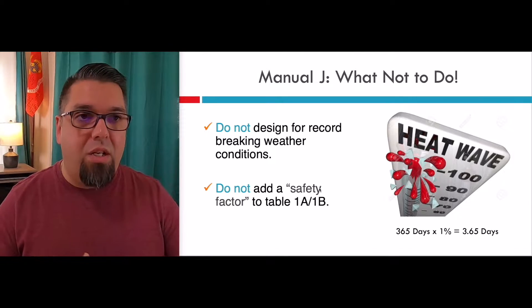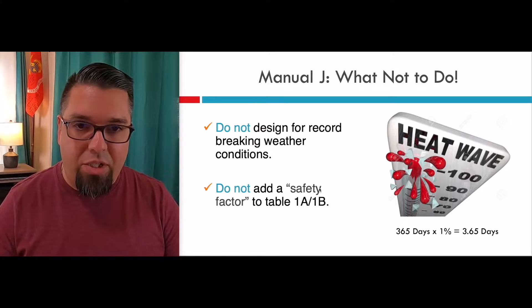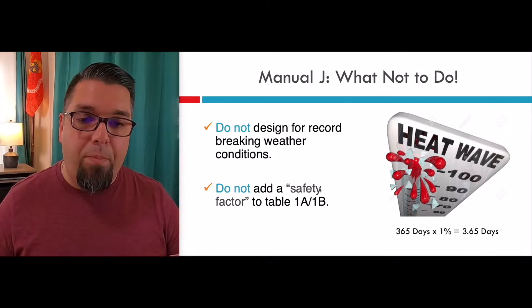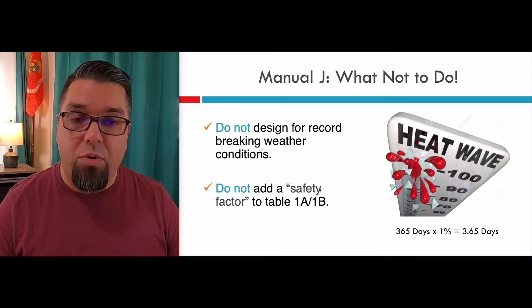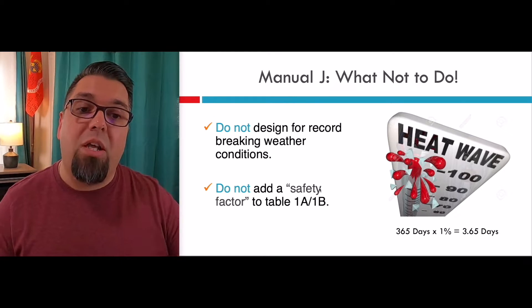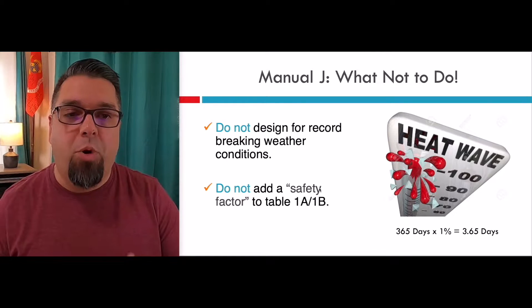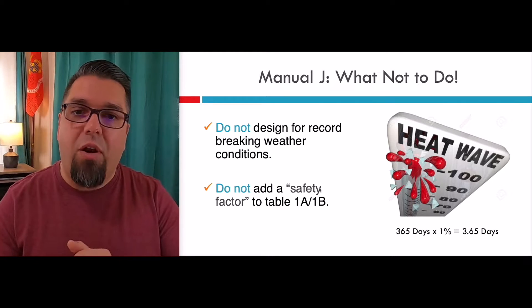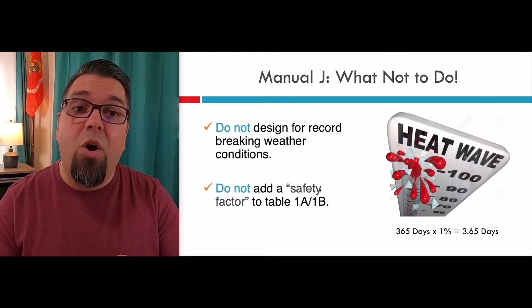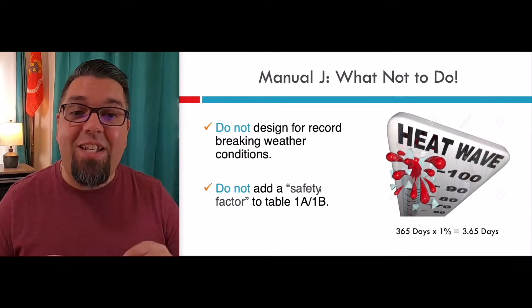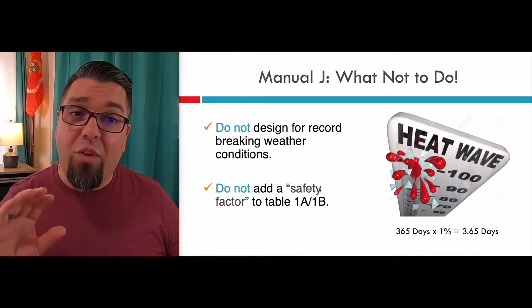We can't keep designing around extreme weather conditions. When there's a heat wave, the system's going to run all the time — prepare your customer for this. It may not keep up by a degree or two on the thermostat, but it's going to be comfortable because it keeps removing moisture. In heating season, we can add humidity to feel more comfortable when it's really cold and dry. Don't design around record-breaking conditions, and don't add safety factors to your outside design temperatures.